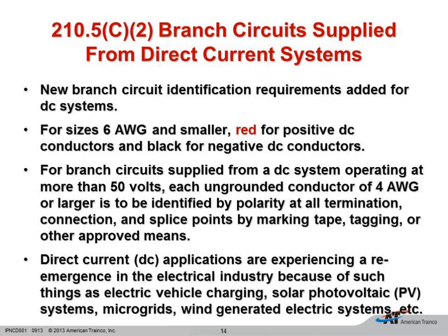Once we get above number 6, then we can identify it in different ways now. We can use wire markers, tags, any approved means that the authority having jurisdiction would accept. But number 6 and below, it has to be continuous red or continuous black, and above that we can use positive or negative signs, however we want to mark it if we get above 6. So some new requirements there for DC color codes.